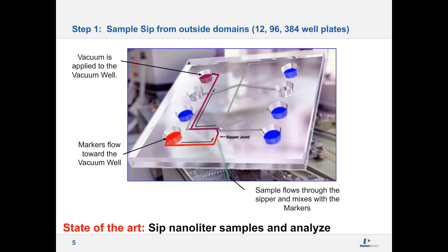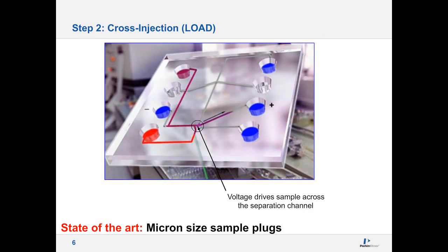The first step is always injection of a sample, ladder, or standard. We apply a vacuum pressure in a well, which brings the sample to the channel, adds the marker to the sample, and it starts flowing. This process takes only a few seconds. We bring the sample to the microfluidic chip and it is ready to be loaded into the gel part of the chip. The state of the art is that we only need nanoliters of sample to analyze, and when we go to the next sample, it cleans up the previous sample and then injects the next one.